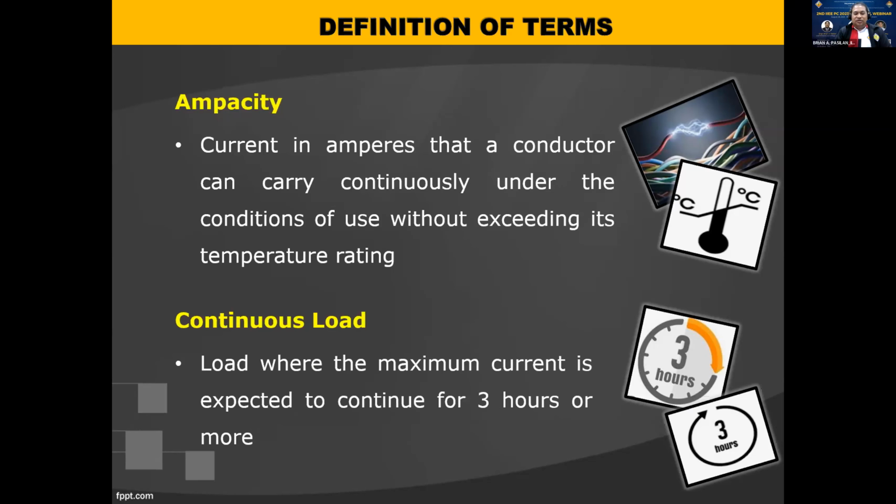Okay, so sinabi ko na kanina, continuous load is the maximum current expected to continue for 3 hours or more, no? So, that's a continuous duty. Ito yung consideration natin, the 3 hours or more. Okay. Then, we'll be talking later about demand factor.